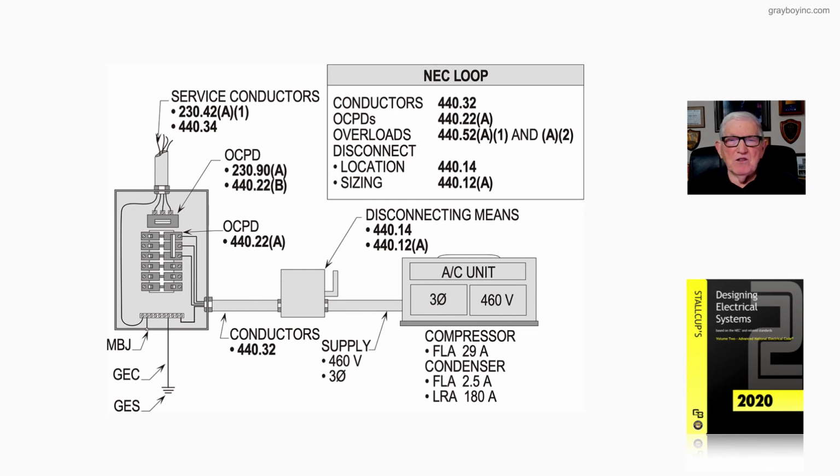Now, with this information, we can look at the second part of this illustration in this figure, 19-3B, and determine what sizing would be required in accordance with a non-automatic circuit breaker and a non-fusible disconnect.